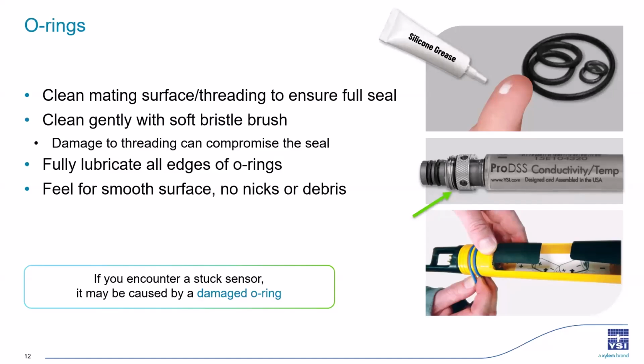But if you're in the field and you have this issue and you don't have a backup O-ring, you can still use your instrument without it. That little O-ring is not helping keep the water seal, to keep it watertight in that seal. It's just there to help the retaining nut, but the retaining nut will still be able to hold the sensor in the bulkhead.